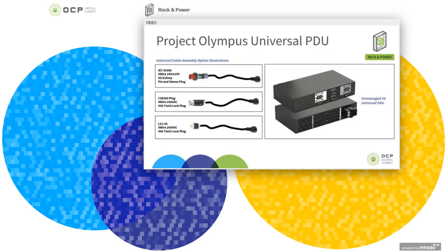And this is the Project Olympus PDU developed for Microsoft. This PDU supports multiple cable input power configurations using a universal cable assembly. The cable assembly or facility side cable will support multiple local power feeds. So the 30, 32 amp Y that Brad discussed, the 50 amp delta, 30 amp three phase delta, we even support single phase facility side cables and country specific cables, like Australia or Japan specific cables.